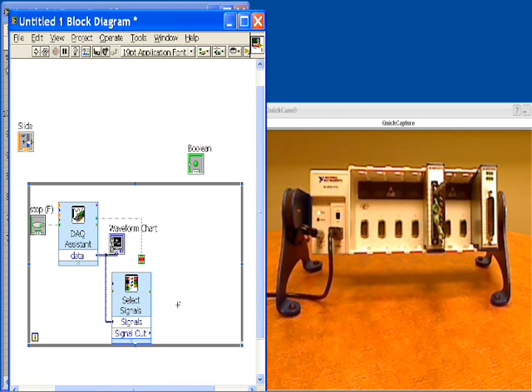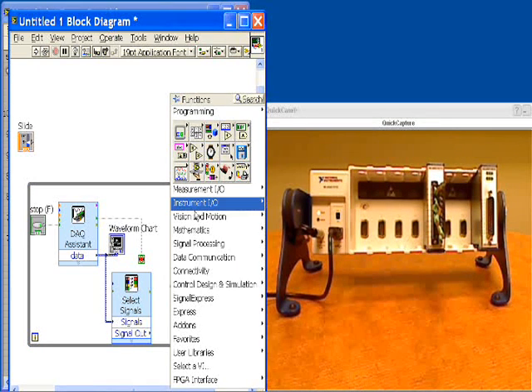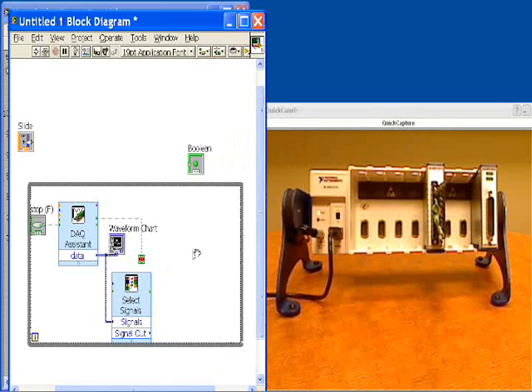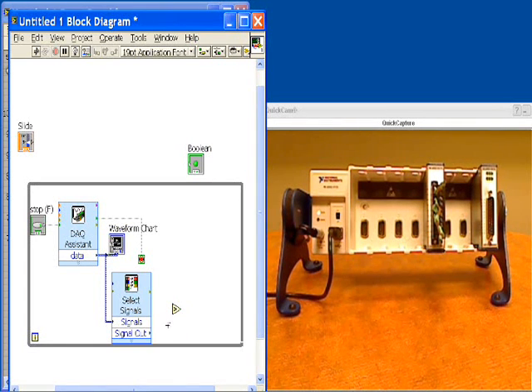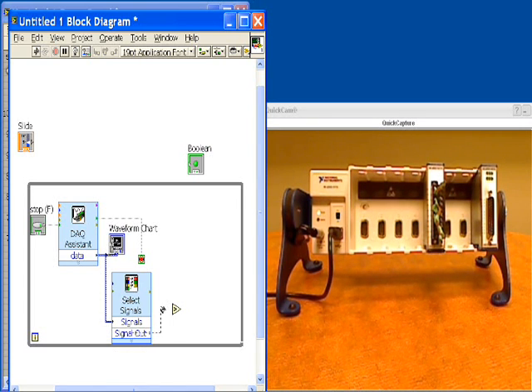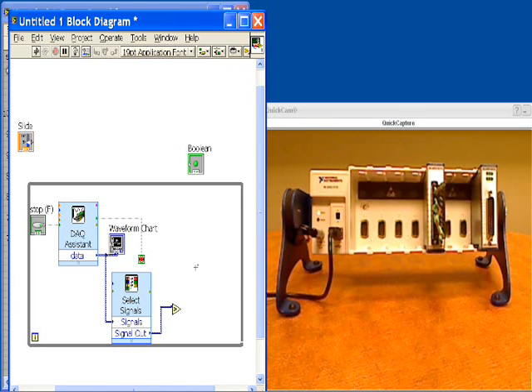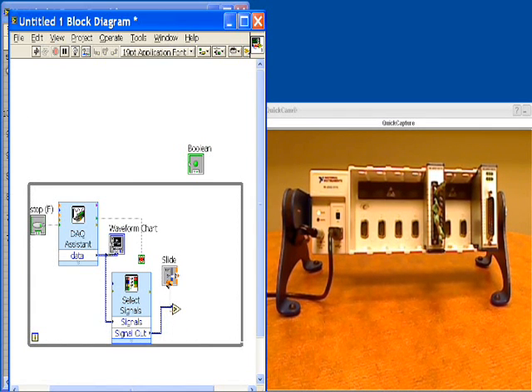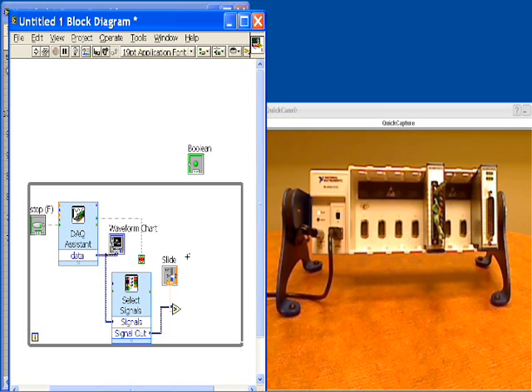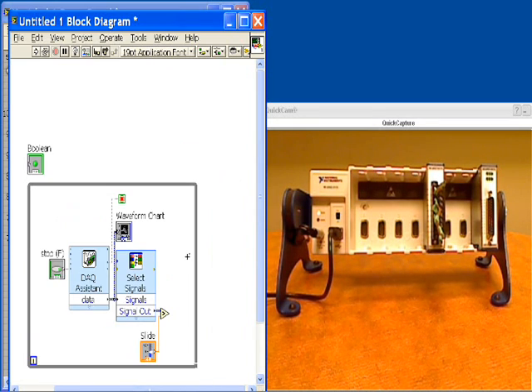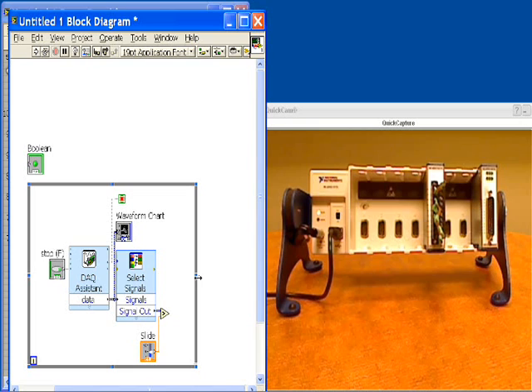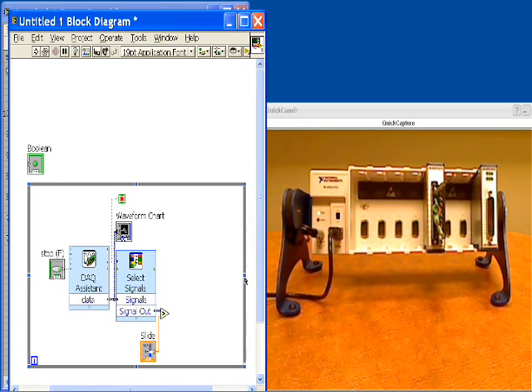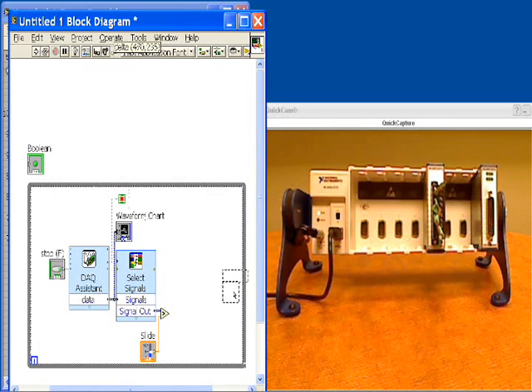So for the alarm limit, we need to compare this to our set point. I'm going to place down a greater than function and bring in my signal out into it. And I need to drag in my slider from the front panel and connect that to the other input. So now the function is going to compare my channel zero to my slider set point. I'm going to do a quick control U to clean up the block diagram.